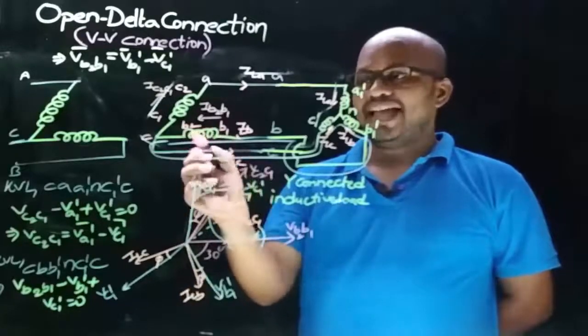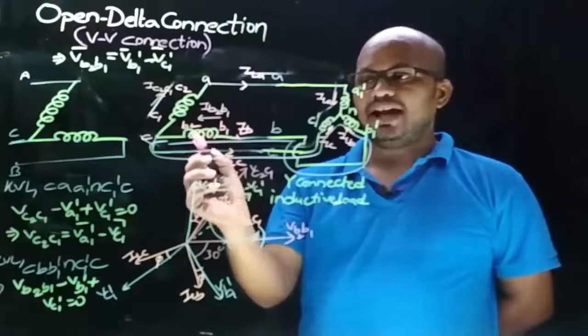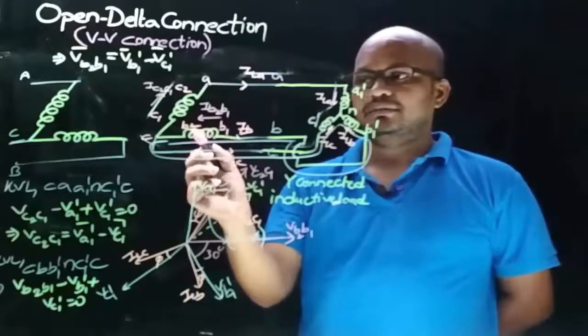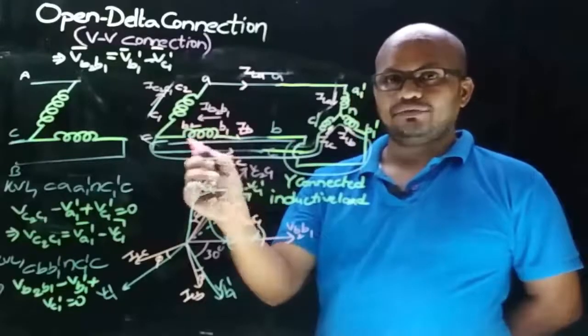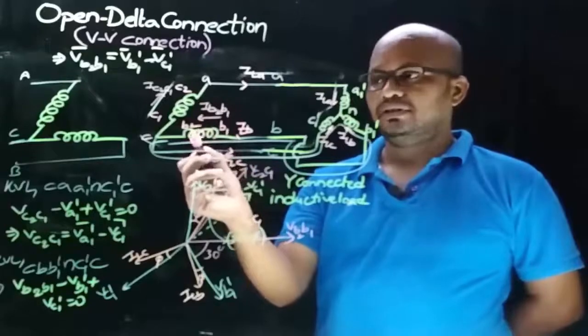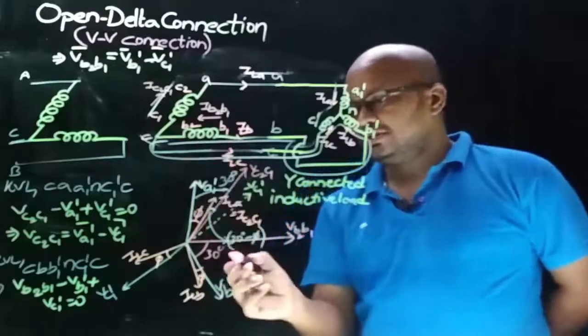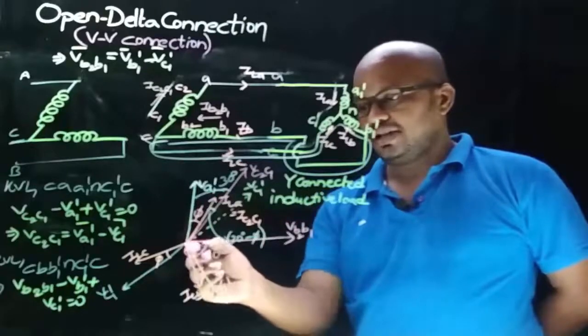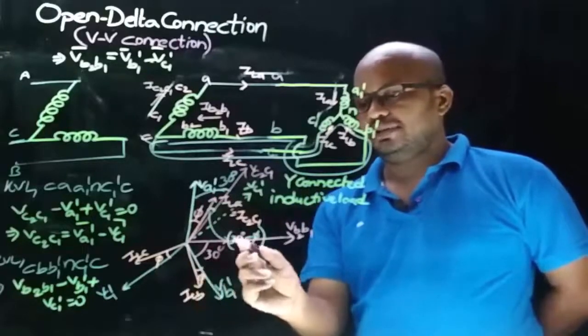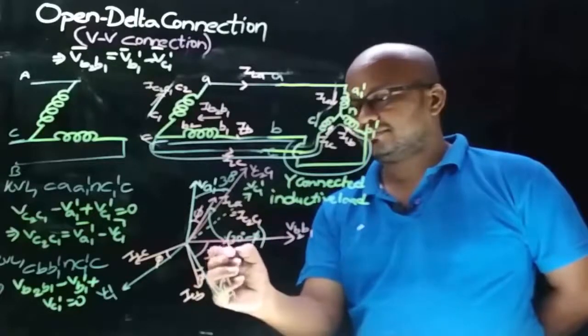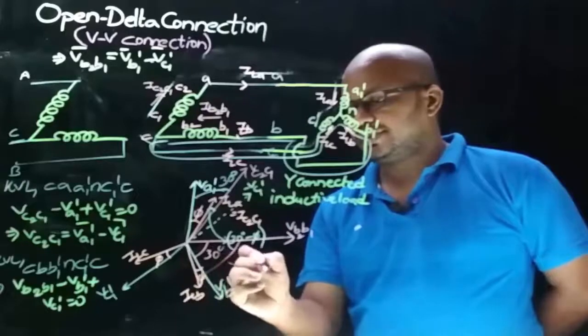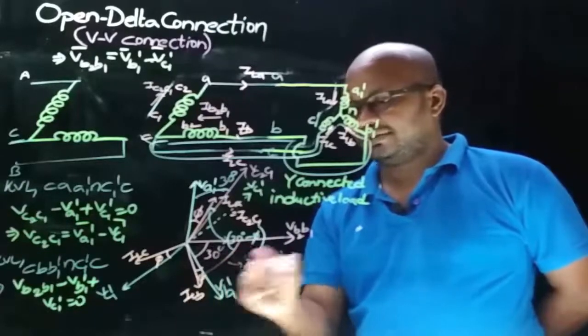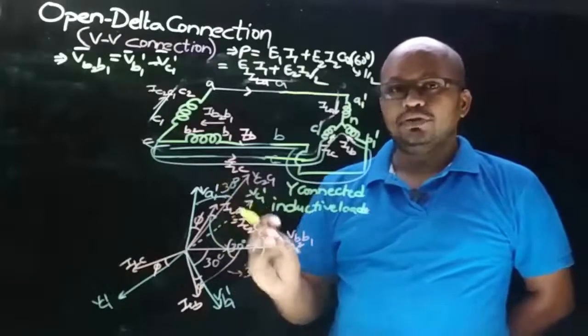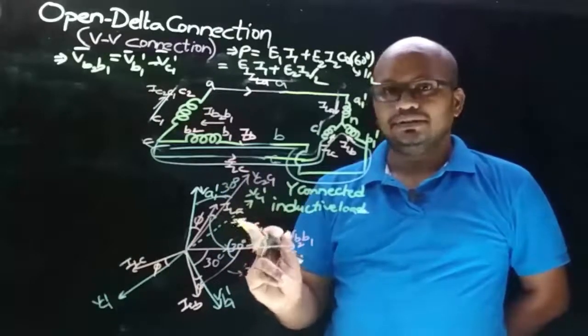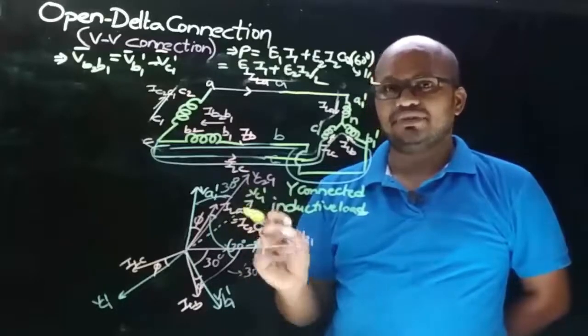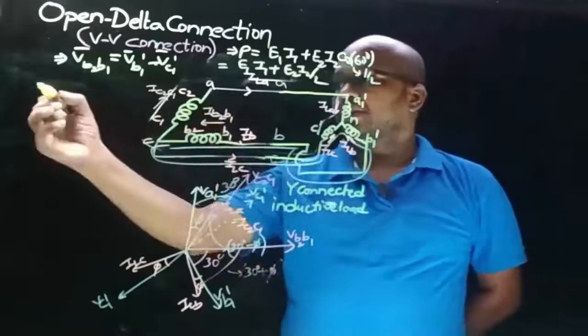And now what we need is the angle between V B2 B1 and I LB. Therefore, to know the operating power factor of this transformer, we need to know the angle between V B2 B1 and I LB. Okay, so this is the V B2 B1 and this is the I LB, and the angle between them is 30 degrees plus phi.